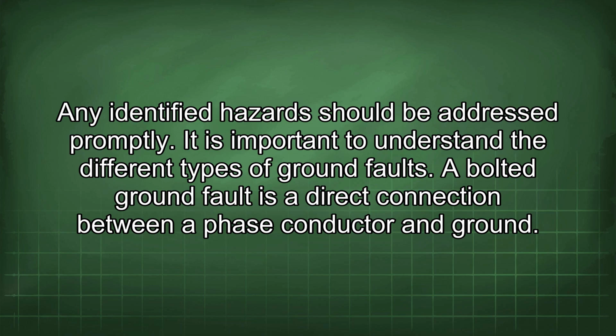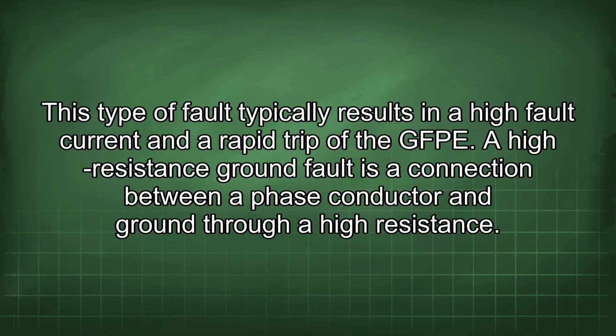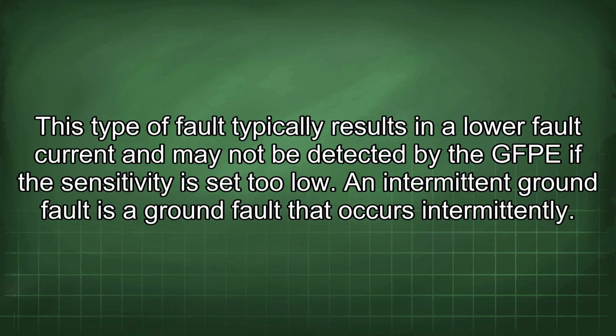It is important to understand the different types of ground faults. A bolted ground fault is a direct connection between a phase conductor and ground. This type of fault typically results in a high fault current and a rapid trip of the GFPE. A high-resistance ground fault is a connection between a phase conductor and ground through a higher resistance. This type of fault typically results in a low fault current and may not be detected by the GFPE if the sensitivity is set too low.